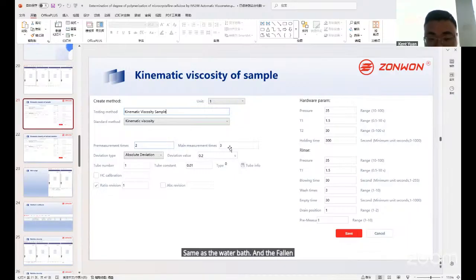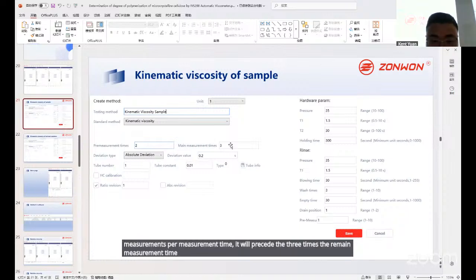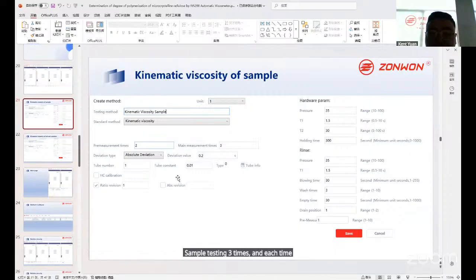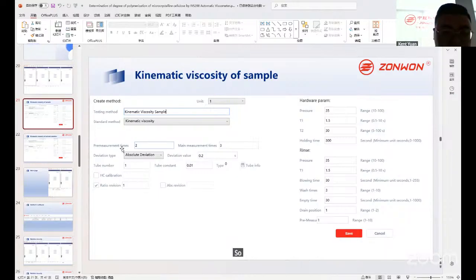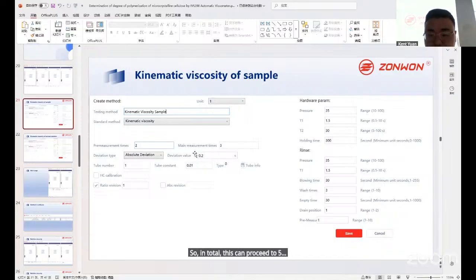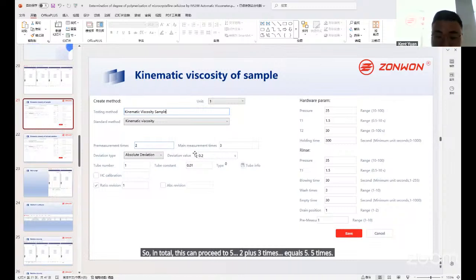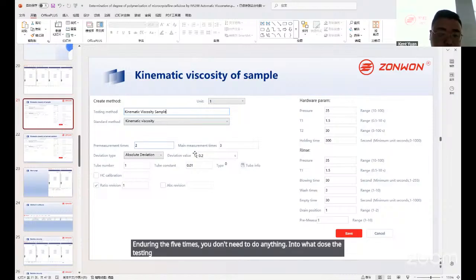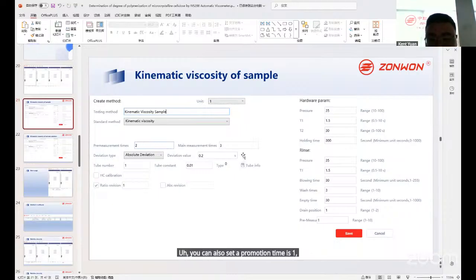And for the main measurement times, 3 times. After 2 pre-measurement times, it will proceed with 3 main measurement times. In this main measurement, it will test the sample 3 times, and each time it will record the flowing time. When it shows a report, it will average the results of the 3 times to get the final result. So in total, it can proceed 2 plus 3 equals 5 times. During the 5 times, you don't need to do anything. It will do the testing automatically and choose the final result automatically. You can also set the pre-measurement time to 1 and the measurement time to 2. It's also okay. It all depends on you. Maximum we can set 9 times and 9 times.